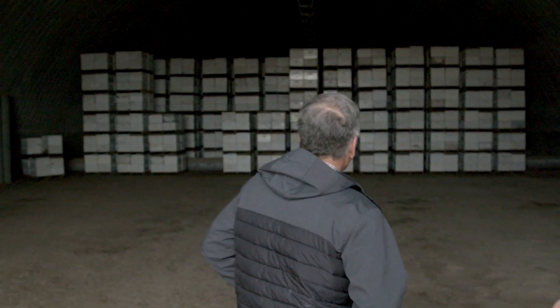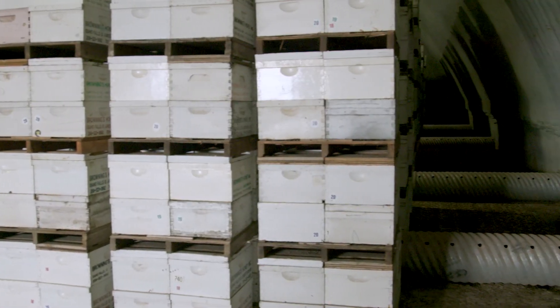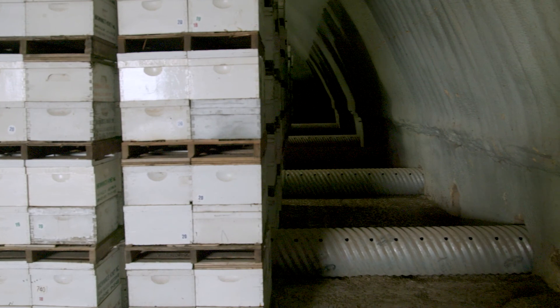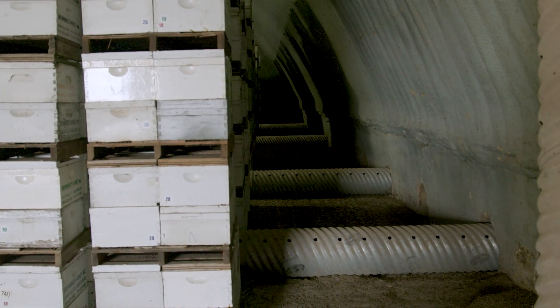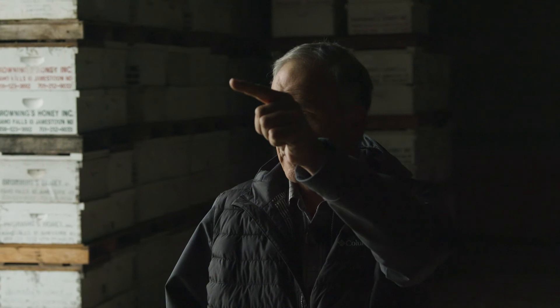This is the bees in the stacks — they haven't been touched yet. They've been in here for 70 days. Ventilation comes from the middle and we put tubes in there, very similar to what they do with potatoes. Those tubes are perforated so air comes out all the way through. We get good ventilation and good circulation. All of the return air gets sucked up through this side over here and back through the system again. Then it blends with outdoor air to control temperature and oxygen levels.